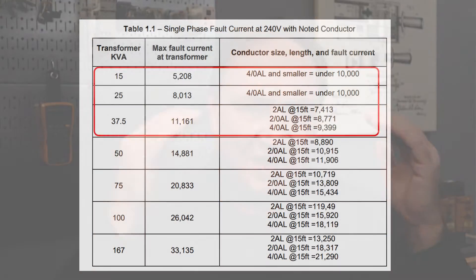Back to the question of why do we need this information. Let's take a look at our code book briefly, and the labeling requirements that we have in 110.9 and 110.10. Notice what the inspector is going to look for in larger gear. And just as an aside, if you only do residential wiring, this is not often a concern as the utility will size their end of the system to stay well below 10,000 amperes fault current, so that even the least expensive electrical gear may be used in residential markets.